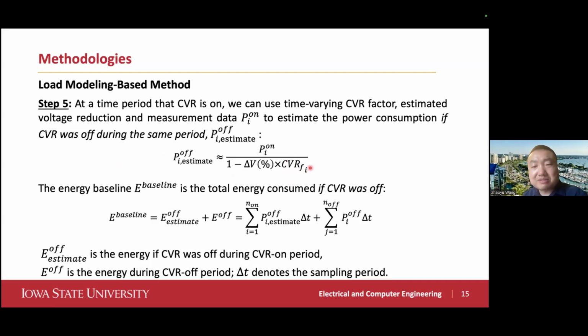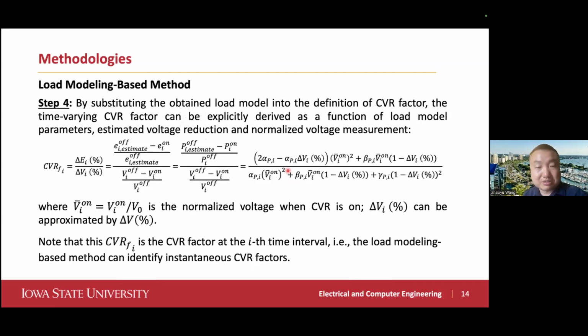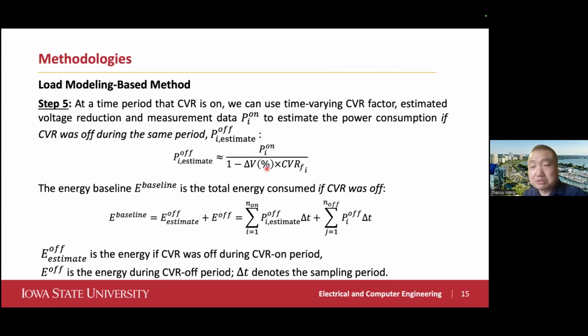Suppose your CVR factor is estimated here, and suppose it's correct. Using this equation, you can reconstruct the load profile, because P is measured, delta V is calculated, and the CVR factor is identified — so you have everything in the equation. You can estimate what the load consumption would be if you didn't have this voltage change, giving you P off estimate.